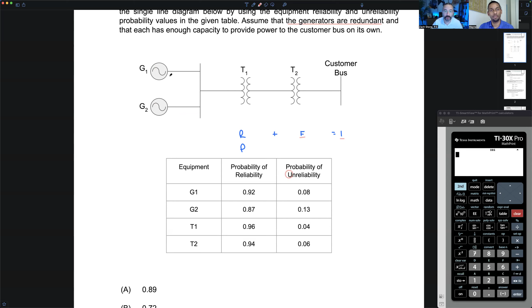Next, I'm going to draw out what's called a reliability block diagram. For this particular problem, it's going to look just like the single line diagram. That's not always the case, but since both generators are redundant, we only need one to provide power to the customer. That lets me model generator number one and number two as parallel—not electrically parallel like in the single line diagram, but parallel from a redundancy standpoint in reliability. Does that make sense? Yes, it does.